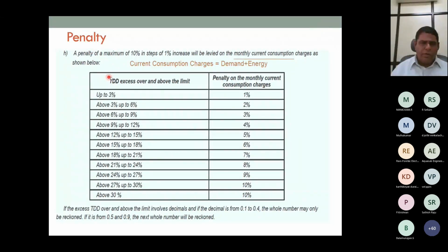So only for TDD, it is clearly mentioned only for TDD. TDD excess over and above the limit. 3% if it is exceeding the limit. The limit we saw already. The penalty will be 1%. It's a ladder penalty, a stepwise penalty. Above 3 up to 6 will be 2%. Like that, the maximum penalty will be 10%.